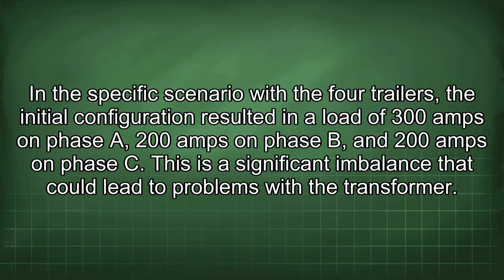In this specific scenario with the 4 trailers, the initial configuration resulted in a load of 300 amps on phase A, 200 amps on phase B, and 200 amps on phase C. This is a significant imbalance that could lead to problems with the transformer.